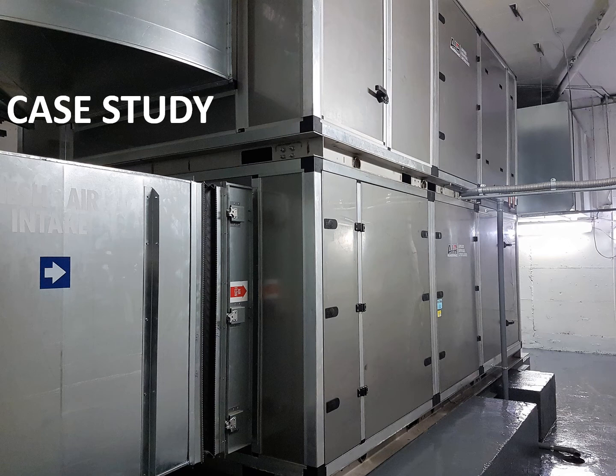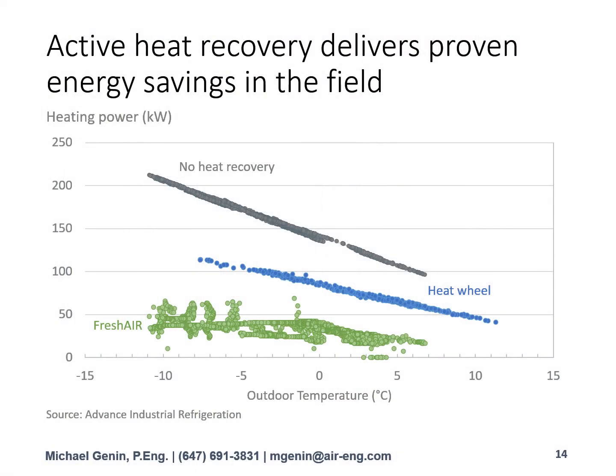So what we did was a third party came in and recorded the data from the existing heat wheel electric heat unit for a few weeks in the winter. The unit was replaced and then the fresh air unit was installed. And after the installation, the data was recorded again. So we really have some good real world data on this unit compared to a previous heat wheel unit. And these are the results from the study.